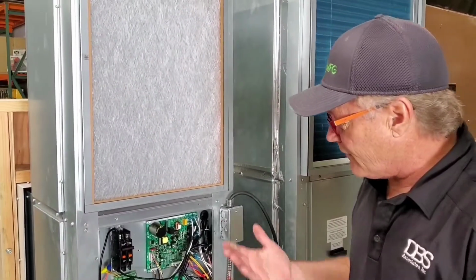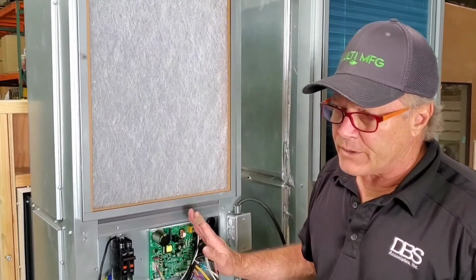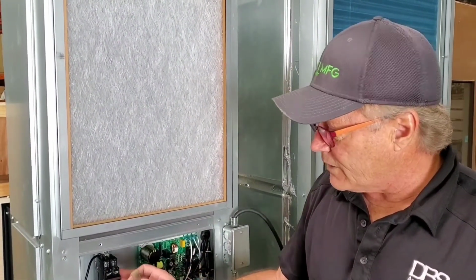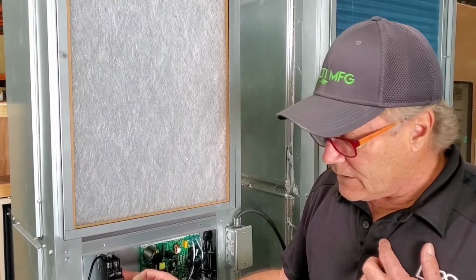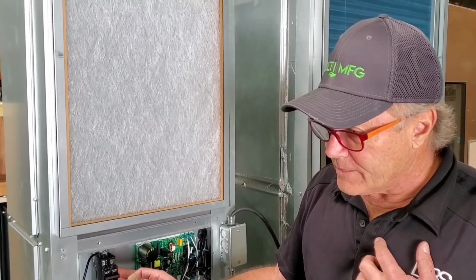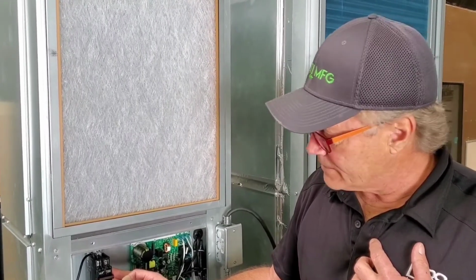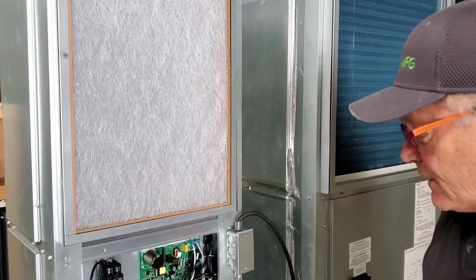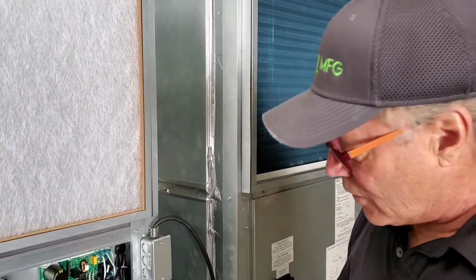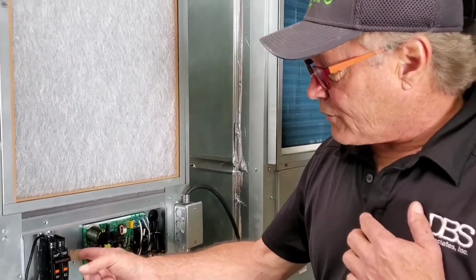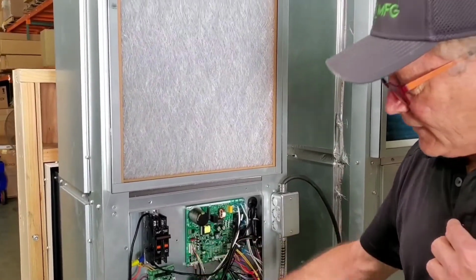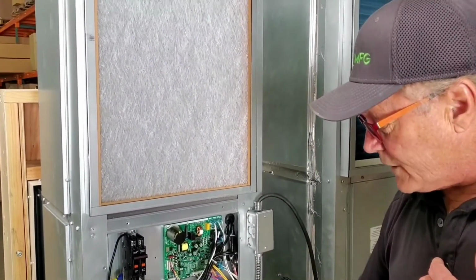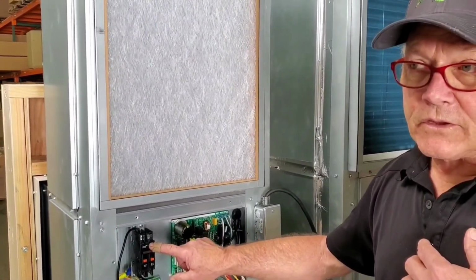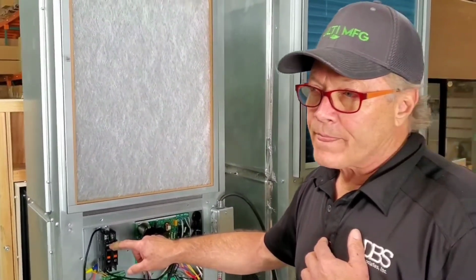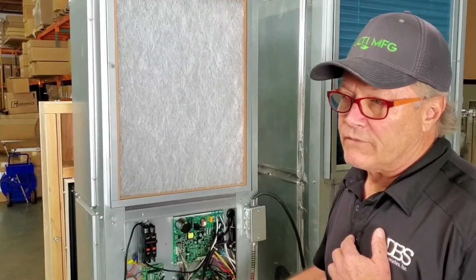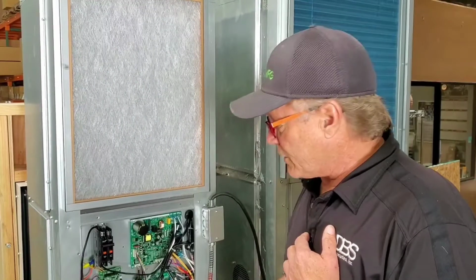What you won't have is, at 40 degrees, you can hear it ramping up a little bit. At 40 degrees, the competition that you're replacing, there we go. Okay, it's done its thing. Now it knows how to operate at a low mode, efficient mode. At 40 degrees, your competition is running only electric heaters. This unit will run down to -5 degrees with only compressor. You're only going to have heat strip operation below -5 degrees, or in the event of a failure of the compressor, or when it goes into defrost.